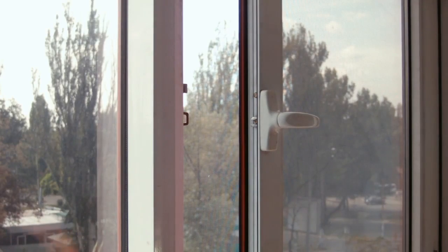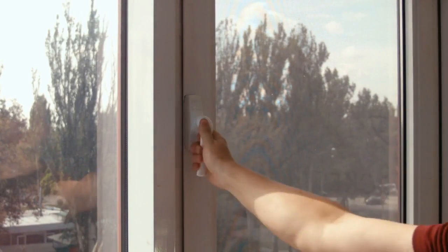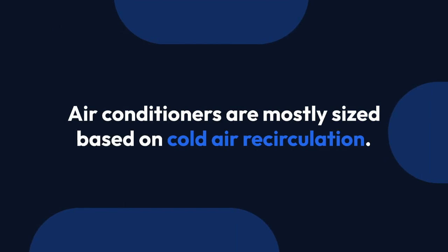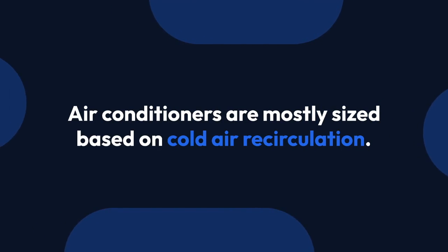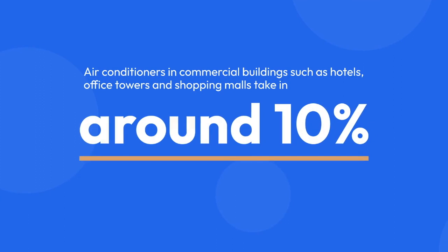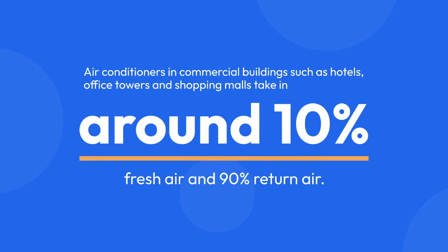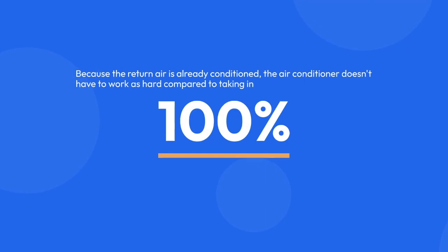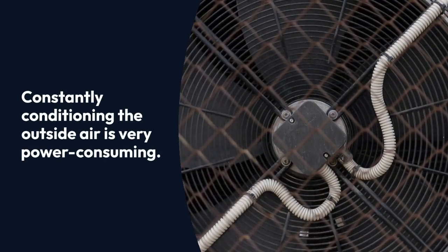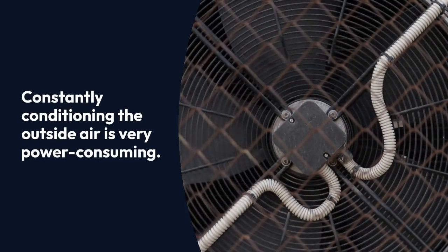Normally, windows and doors need to be closed when air conditioners are in operation. It is because air conditioners are mostly sized based on cold air recirculation. Most of the time, air conditioners in commercial buildings such as hotels, office towers and shopping malls take in around 10% fresh air and 90% return air. Because the return air is already conditioned, the air conditioner doesn't have to work as hard compared to taking in 100% fresh air. In addition, constantly conditioning the outside air is very power consuming for the air conditioner because of wide temperature differences.